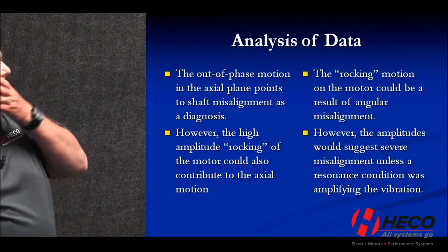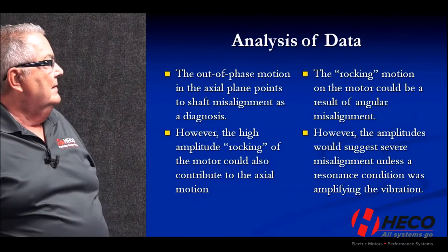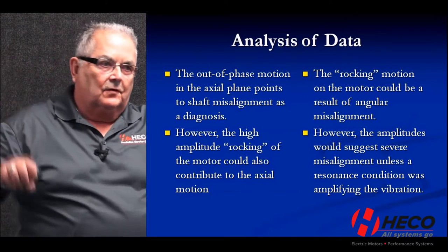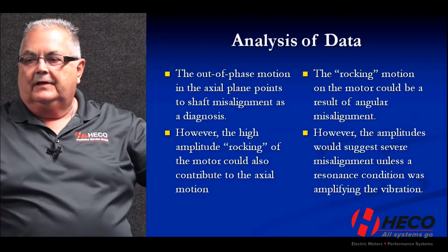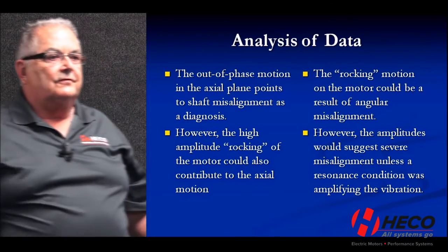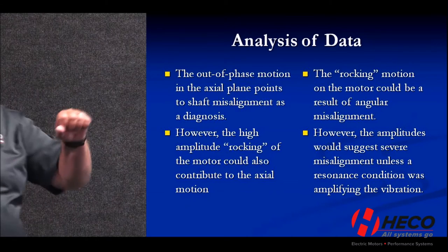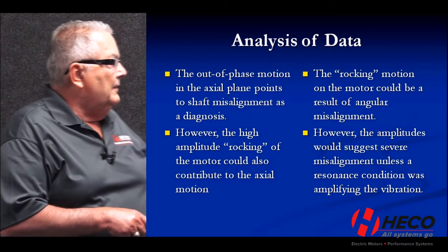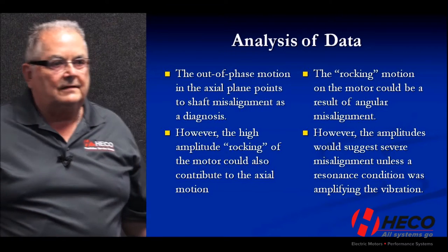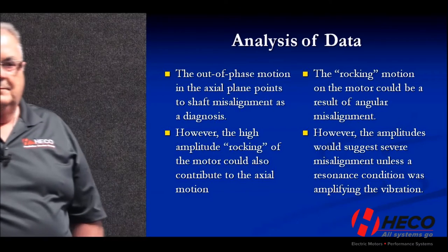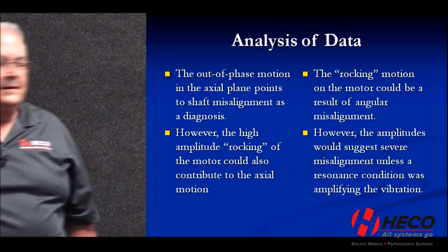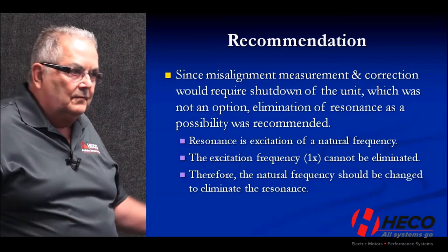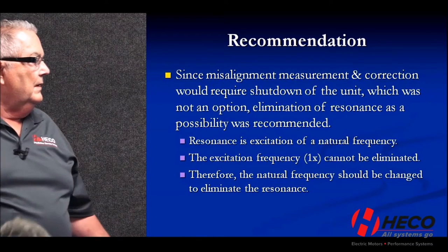Looking at this data, the motor appears to have a rocking motion in the vertical direction, which is where the high vibration is. If you have a rocking motion, that's going to give you some axial motion too — which might explain why both vertical and axial are high while horizontal is fine. So we said: either we have severe misalignment or resonance. We'd already checked the alignment, and checking it again would have required a shutdown they didn't want.